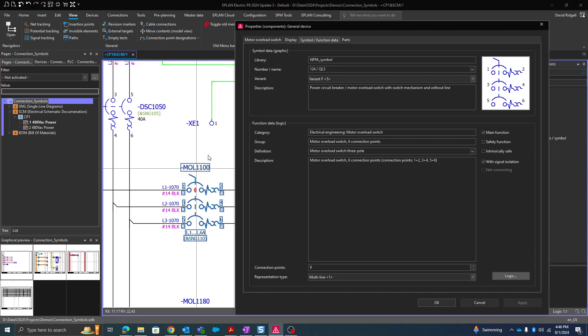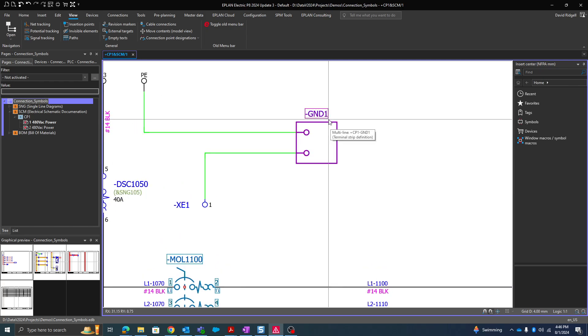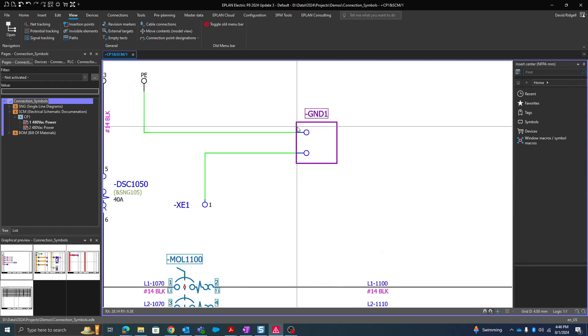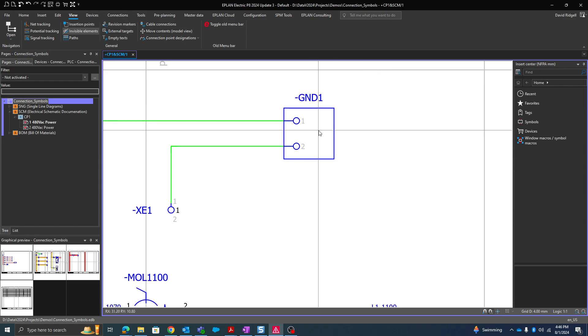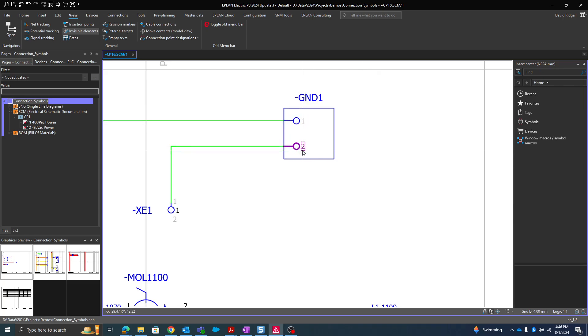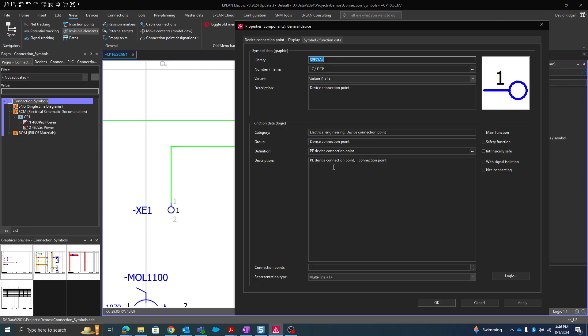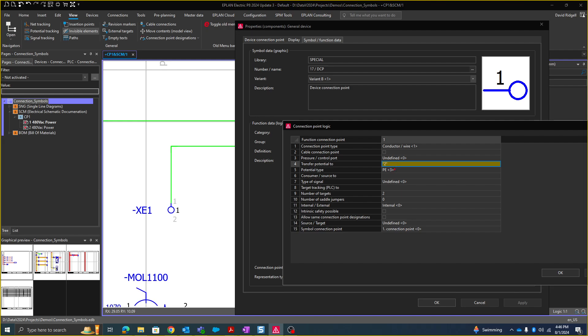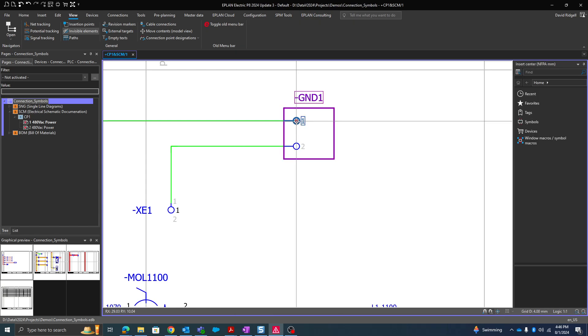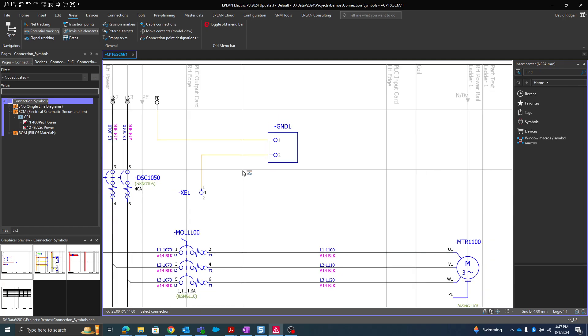But what about more complex devices like this? We have here three symbols that form this one device. We have the black box and the two device connection points. You turn on the invisible elements, you'll see that this is connection point 1, this is connection point 2. So I'm going to go into the properties of connection point 1 and then go into the logic. And here you'll see when we want to transfer to a different symbol within the same device, we're going to put it in these double quotes. And then I'm going to do my potential tracking just to verify that that works and it does.